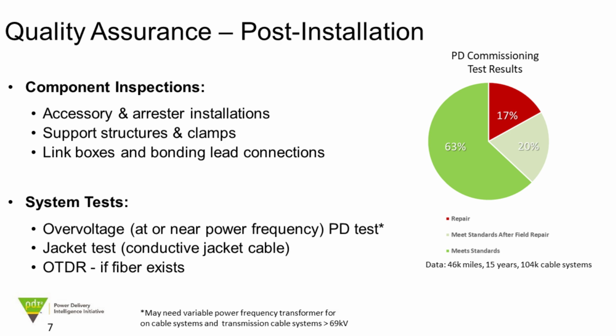This is the medium voltage data over 104,000 cable systems assessed in the field with a power frequency PD test. And you can see that 63% met industry expectations. For example, IEEE 404 for joints, which would be no partial discharge to 1.5 times operating voltage with 5 pC sensitivity, for example. And after mitigation, after fixing what could be repaired there on site, even 17% were left as substandard. So it's a significant problem.